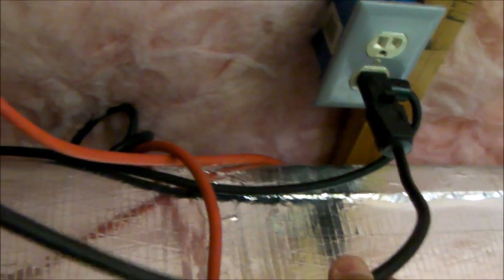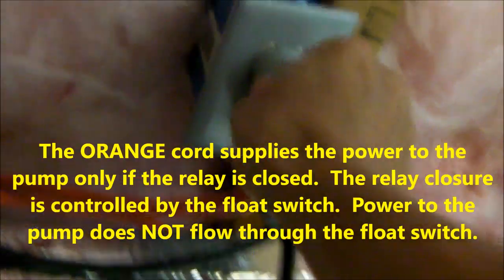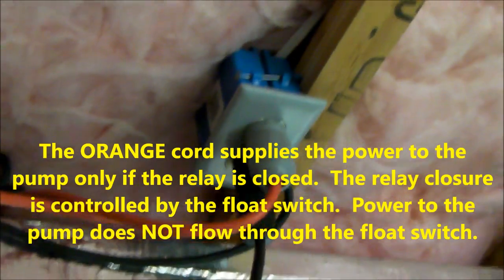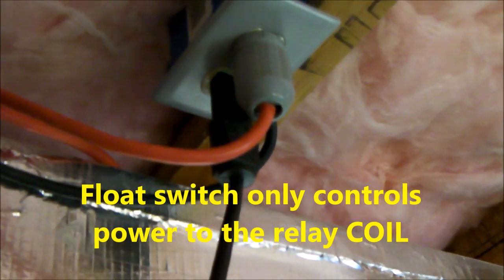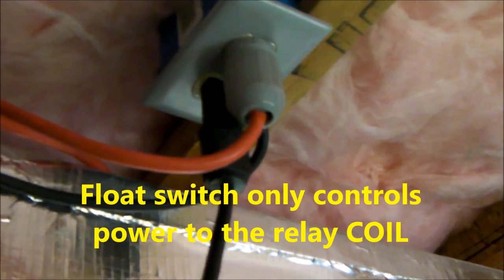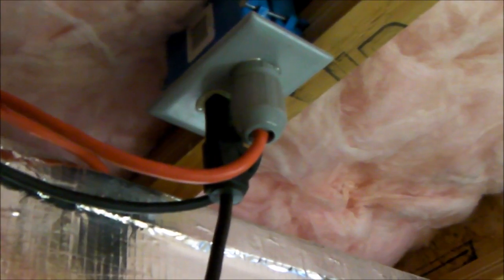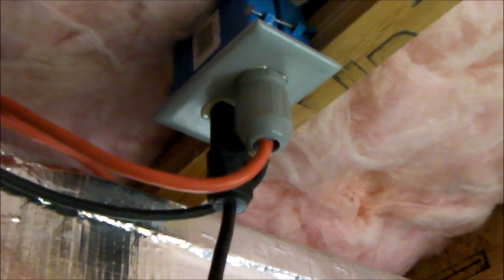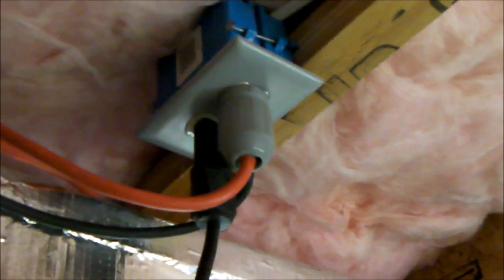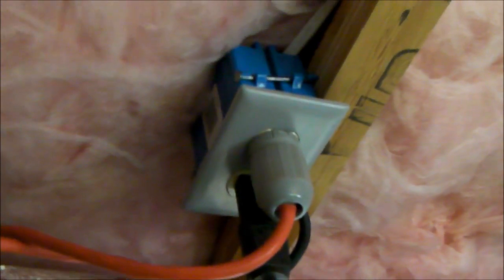Power to the relay coil control is provided by this black cord. And then the last cord I'm going to plug in here is this orange cord. This orange cord is power that goes to the relay contacts, and the relay contacts provide power to the pump. So what's happening here is that the float switch is only controlling power to the relay. And the relay draws a very, very small amount of current. And therefore, the float should last a long time because it is not anywhere close to being stressed. It's only controlling literally milliamps of current to energize the coil of the power relay or the coil of the contactor.